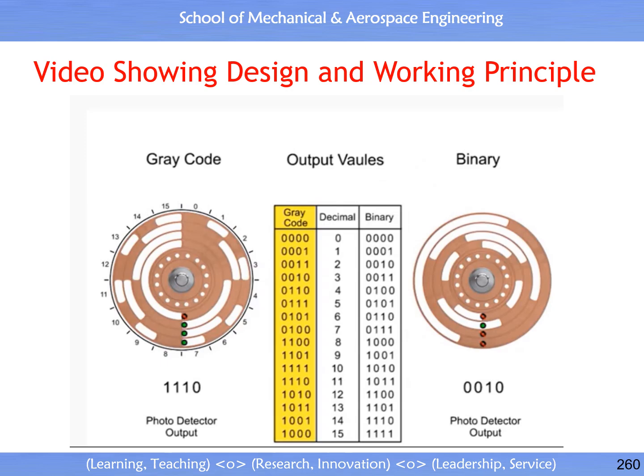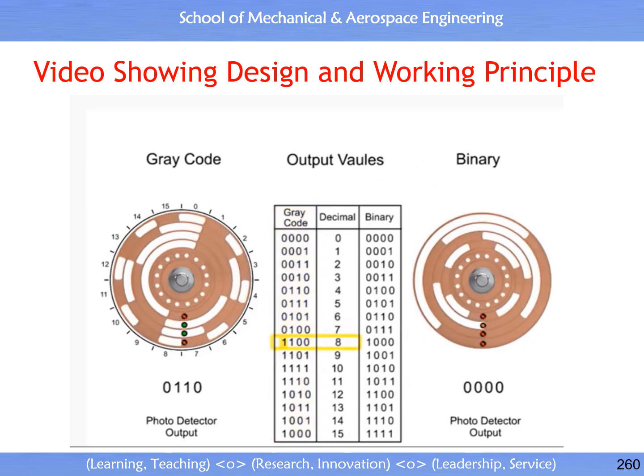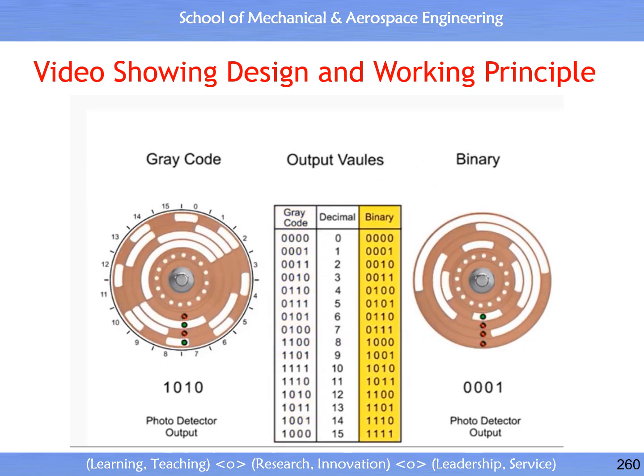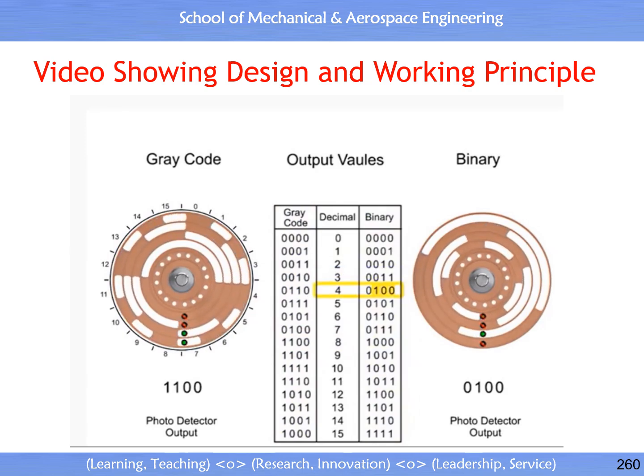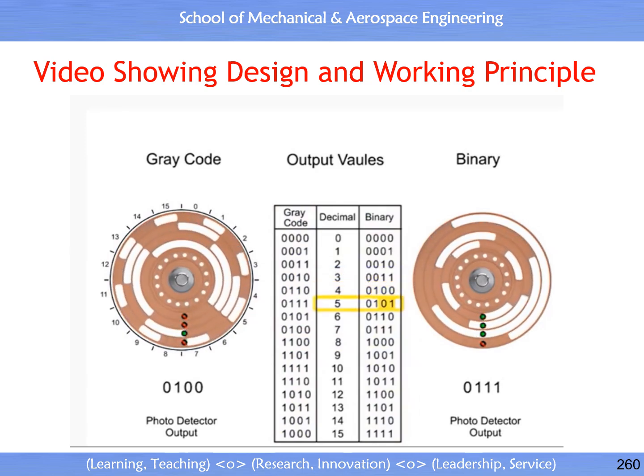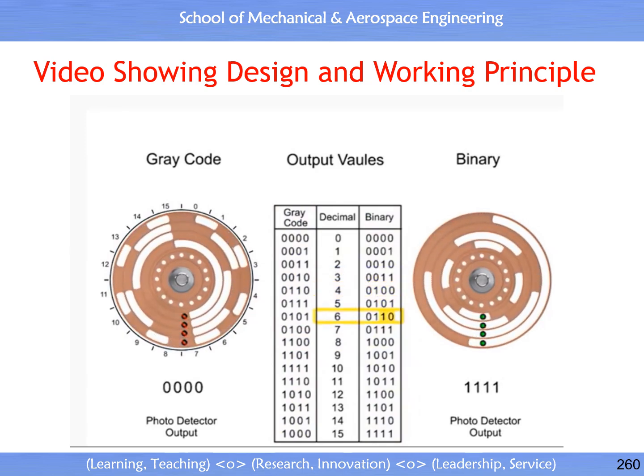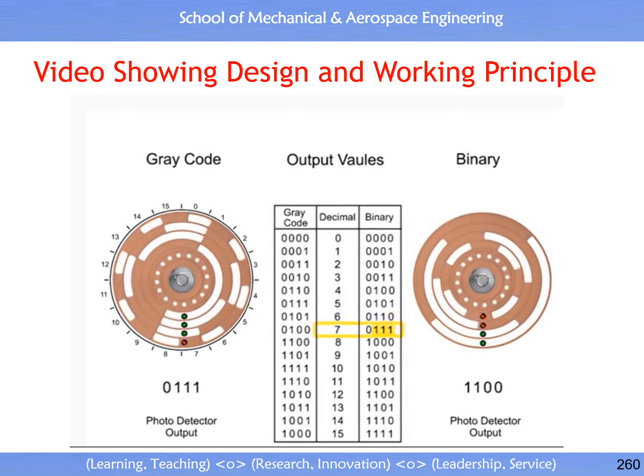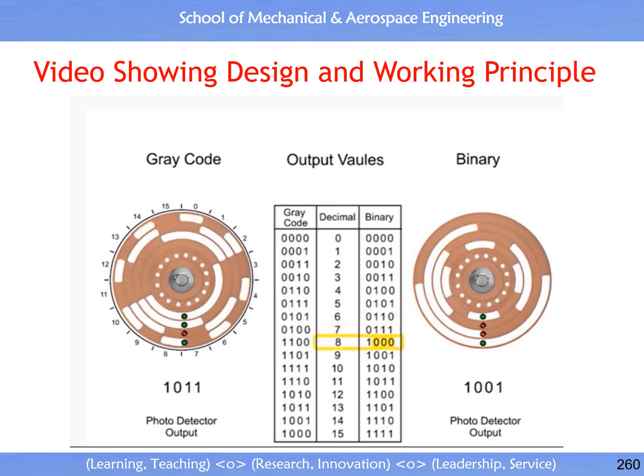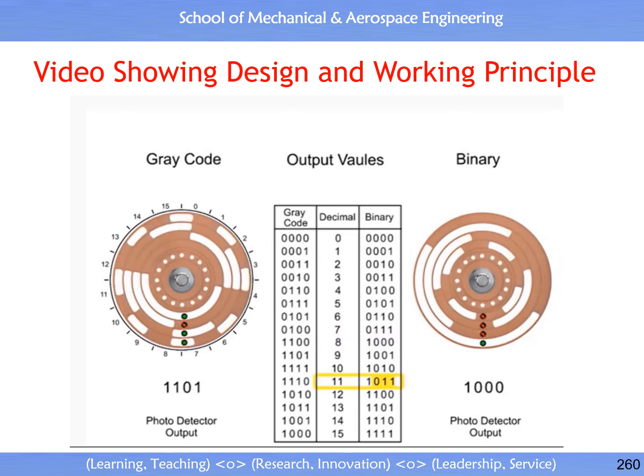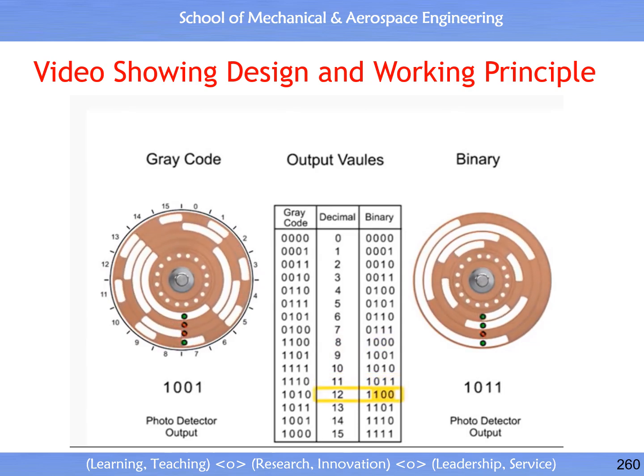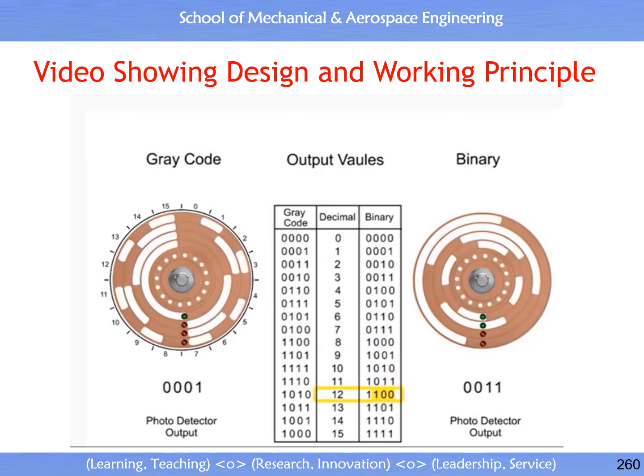Gray code is designed so that only one bit changes at a time, contrary to a binary system where one or more numbers change in the word. By changing more than one number of the word at a time in the binary system, the possibility of positioning errors is greater, leaving gray code the preference in precision applications.